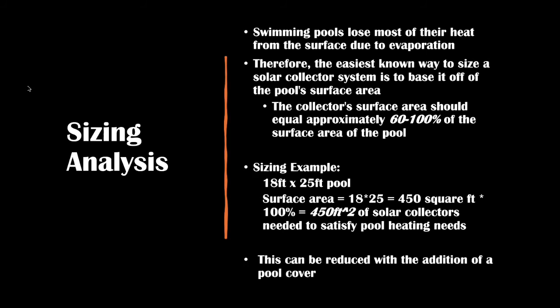Evaporation takes a tremendous amount of energy in the form of heat. Therefore, swimming pools lose most of their heat from the surface due to evaporation. Because of this, the easiest known way to size a solar collector system is to base it off of the pool's surface area. The collector's surface area should equal approximately 60 to 100% of the surface area of the pool. For example, an 18 by 25 foot pool has a surface area of 450 square feet, so you can multiply this by 100% to be conservative and come to the conclusion that 450 square feet of solar collectors should be enough to suffice. The addition of a pool cover can greatly improve the heat loss and therefore allow for a smaller size collector as well.